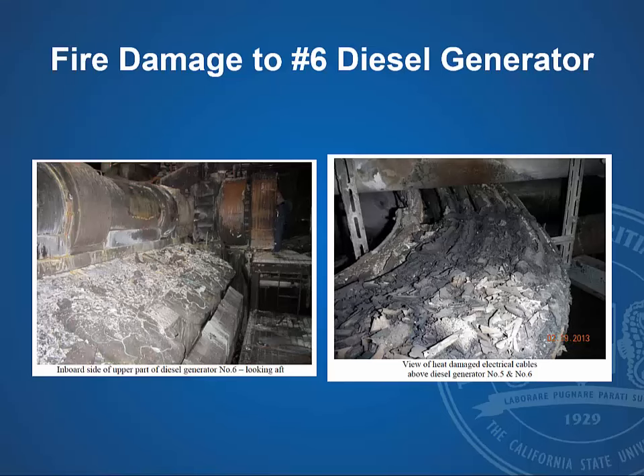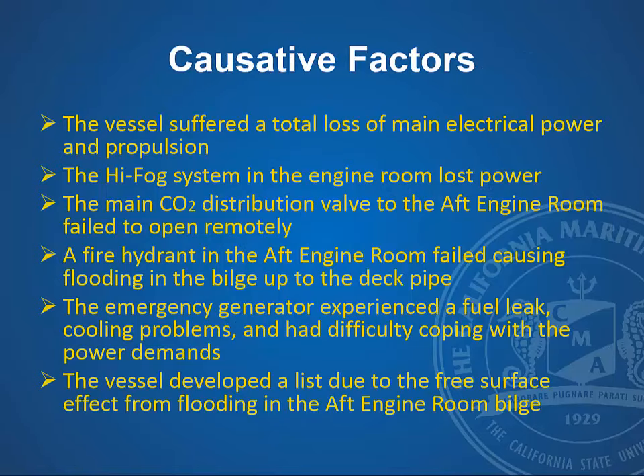So this is a look at the fire damage. On the left, that's the number 6 generator, and on the right, that's your cabling supplying power to the main switchboard. So let's look at some of the factors that were very instrumental in going from a minor incident to a major incident in this fire. The vessel suffered a total loss of main electrical power and propulsion. The Hi-Fog system, the primary one that would have shut down this fire very quickly, lost power because the wiring was burned and power was cut off to the main switchboard.